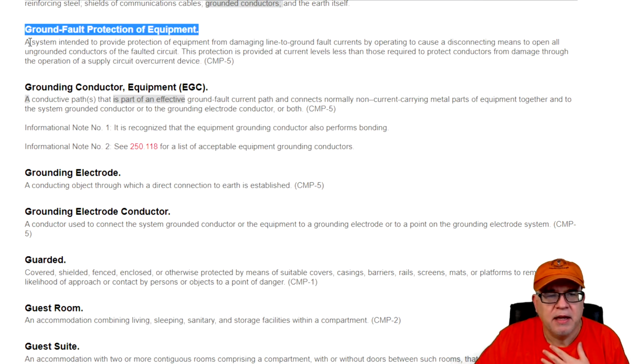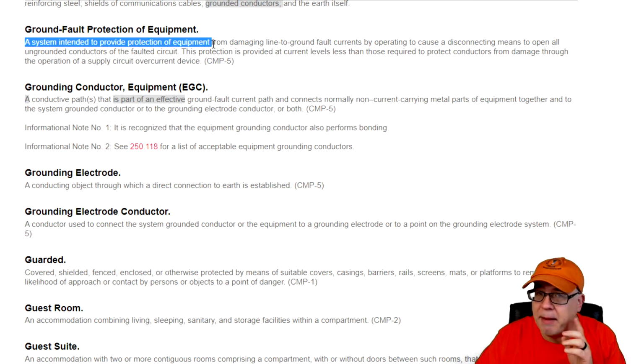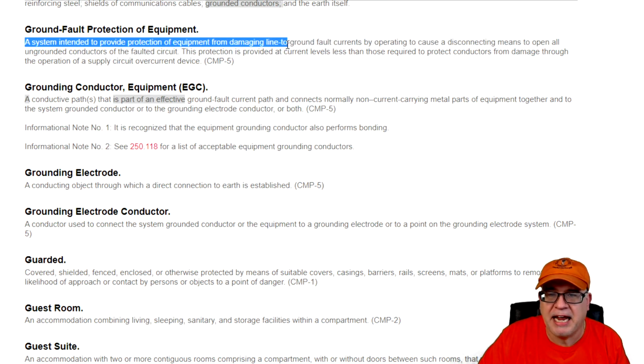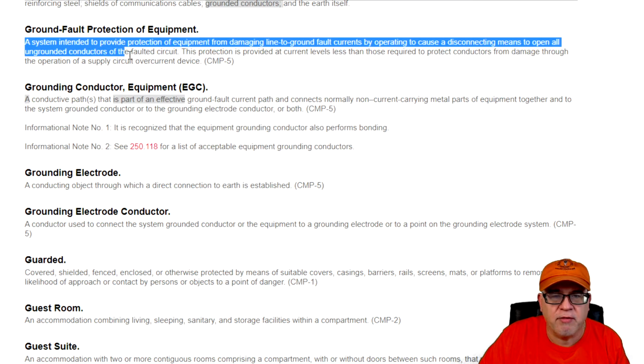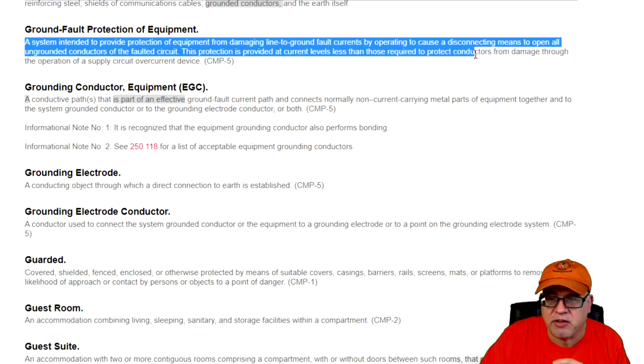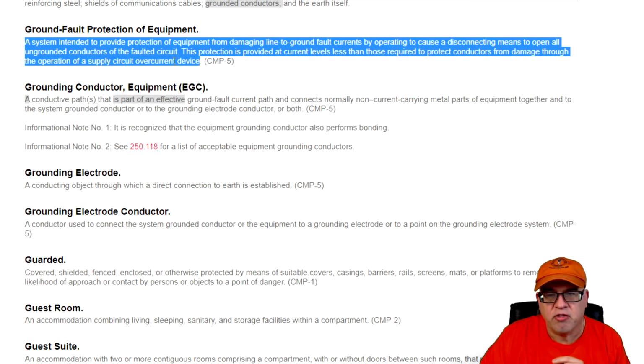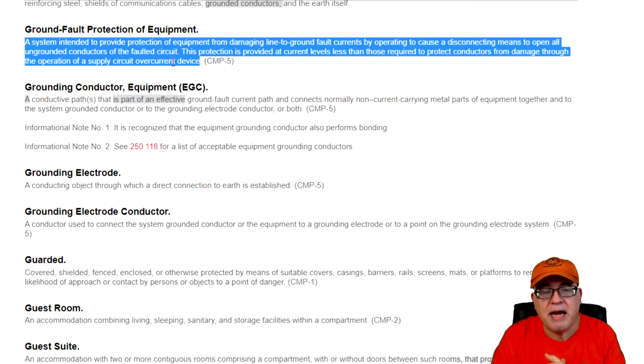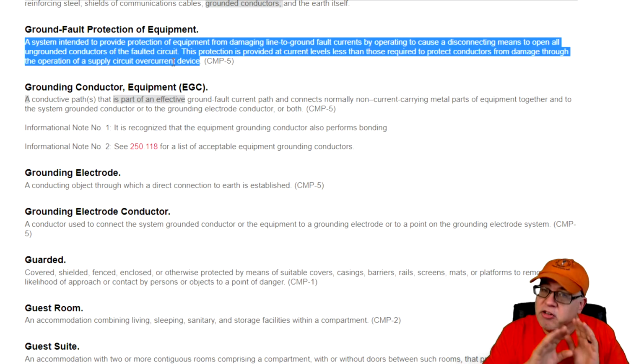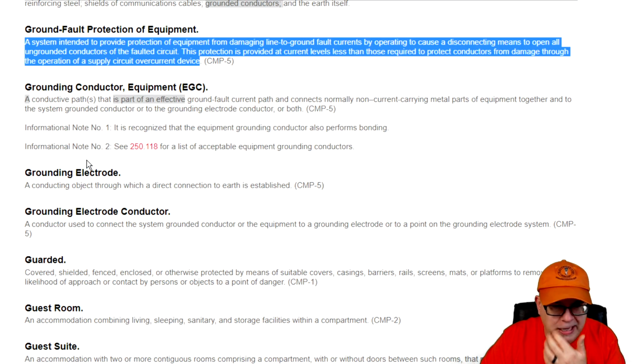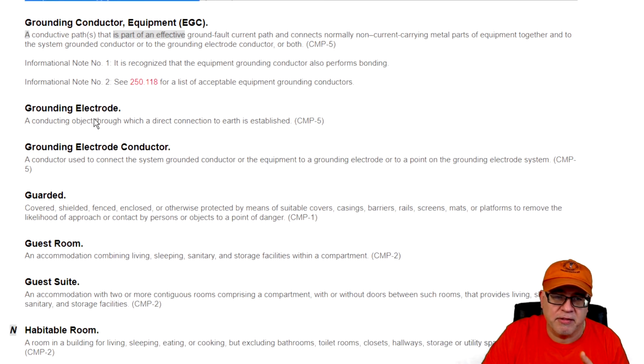Now, what is GFP? It's a system intended to provide protection of equipment, not personnel, from damaging line-to-ground fault currents by operating to cause a disconnecting means to open the ungrounded conductors of a faulted circuit. This protection is provided at current levels less than those required to protect conductors from damage through the operation of a supply circuit overcurrent device. So again, it's less than when we're sizing overcurrent devices, okay? So just keep in mind, GFP is different than GFCI. Just can't reiterate that enough. And a lot of times it's real easy for us to just throw things out there and not realize that there is a difference.